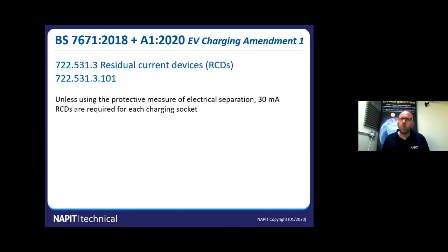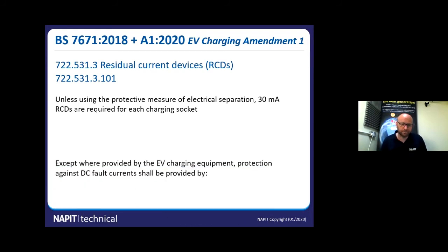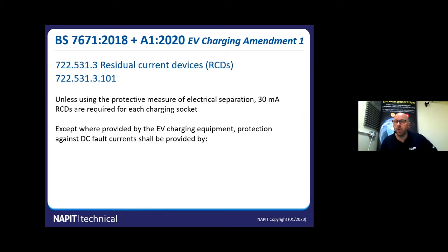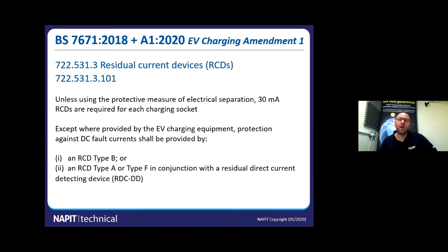So next up we're going to look at RCDs. Unless you're using the protective measure of electrical separation, you need a 30 milliamp RCD for each charging socket. And except where provided by the EV charging equipment, the protection against DC fault current shall be provided by a type B RCD, or a type A or F RCD in conjunction with a residual direct current detecting device, the RDCDD. So the new thing here is the type F and also the RDCDD. That was new to these regulations.